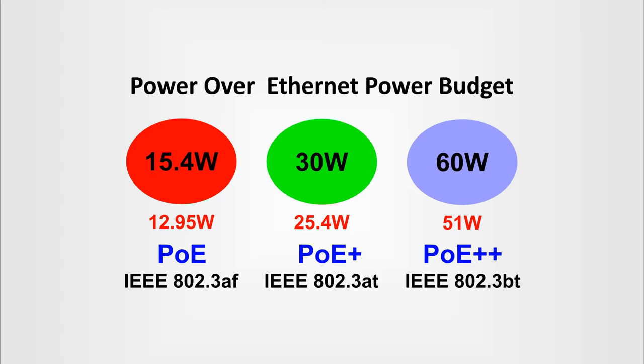PoE switches generate 15 W per port, PoE+ switches generate 30 W per port, and PoE++ switches generate 60 W per port. These are maximum values; practically we should use 12.95 W per port for PoE, 25.4 W per port for PoE+, and 51 W per port for PoE++ switches, since some power is dissipated in the cables.